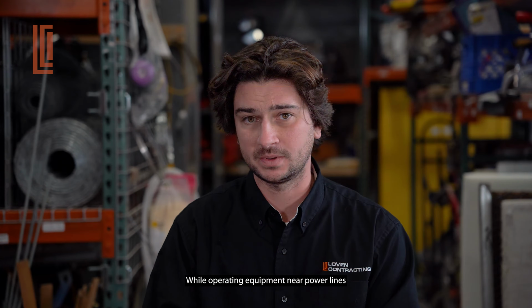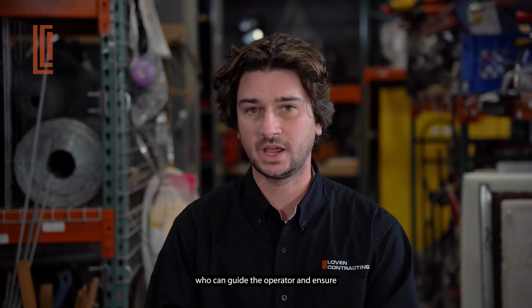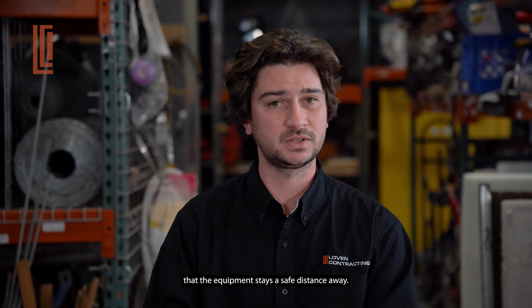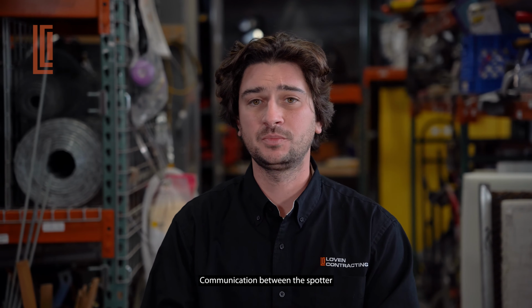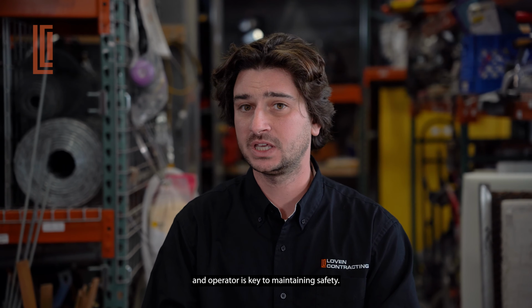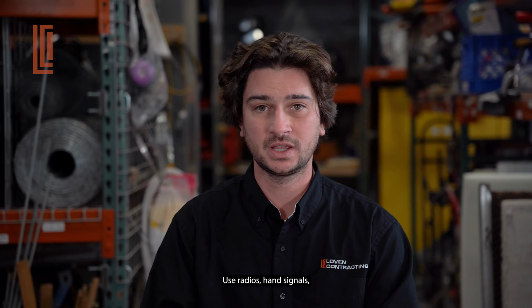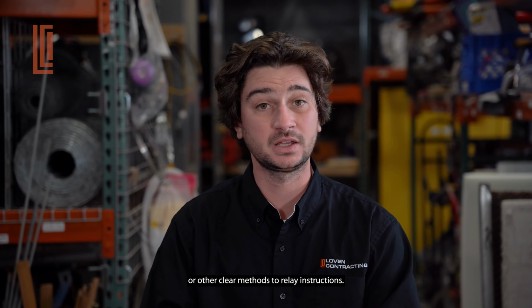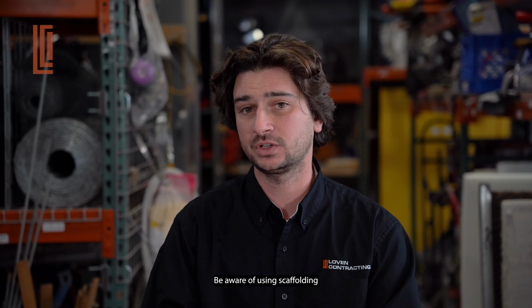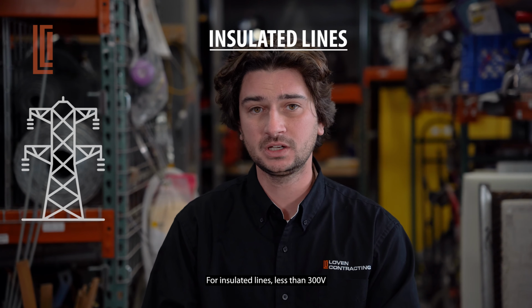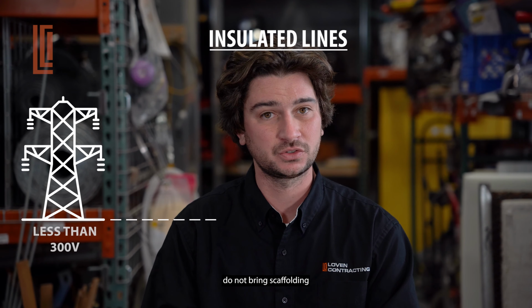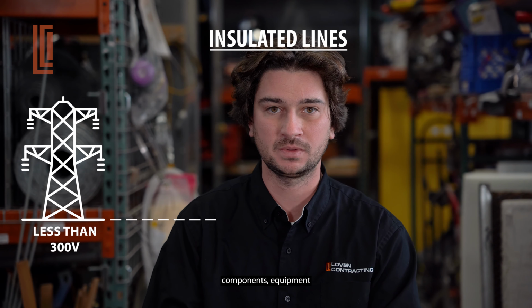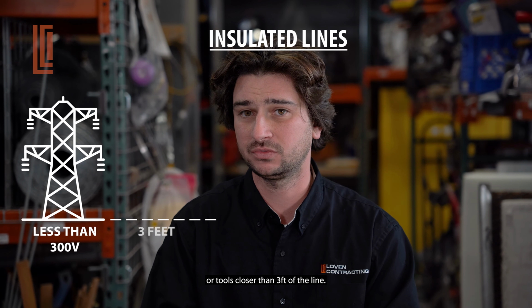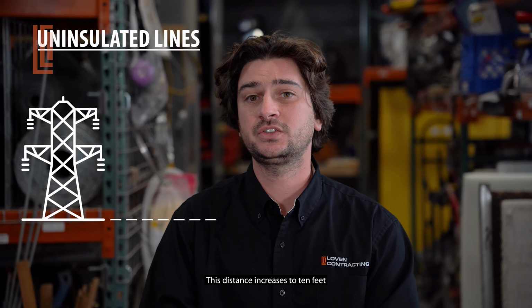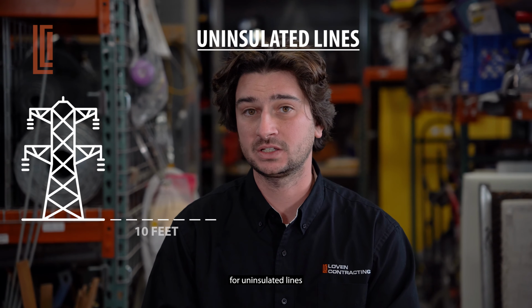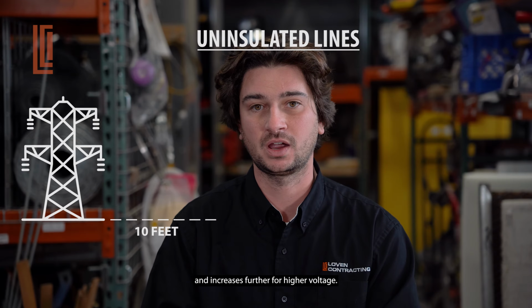While operating equipment near power lines, use a spotter who can guide the operator and ensure that the equipment stays a safe distance away. Communication between the spotter and operator is key to maintaining safety. Use radios, hand signals, or other clear methods to relay instructions. Be aware of using scaffolding near overhead power lines. For insulated lines less than 300 volts, do not bring scaffolding components, equipment, or tools closer than 3 feet of the line. This distance increases to 10 feet for uninsulated lines and increases further for higher voltage.